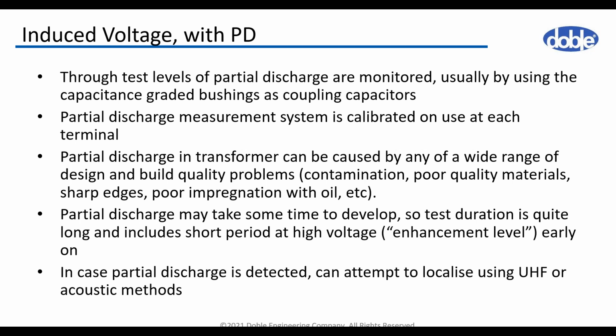The partial discharge system is calibrated before use on each terminal. In case elevated PD levels are detected, further investigation is planned, or should be planned, to localize the problem, as different techniques might be used. Suitable techniques for this purpose are the UHF probe and also acoustic partial discharge measurement.